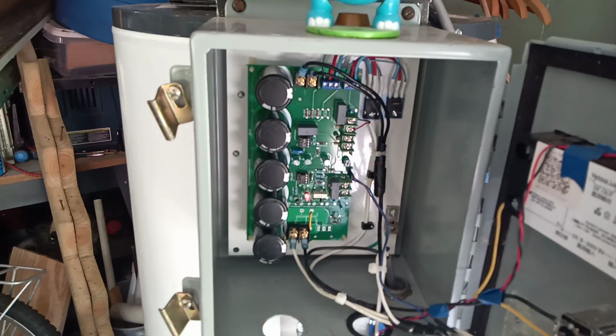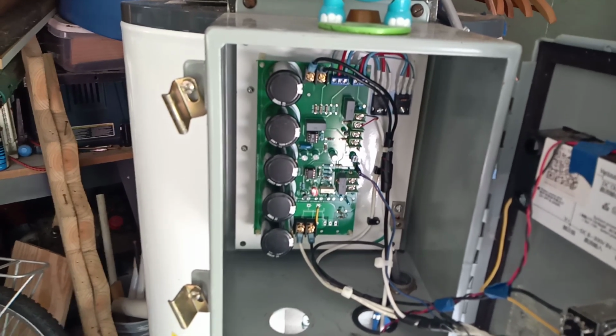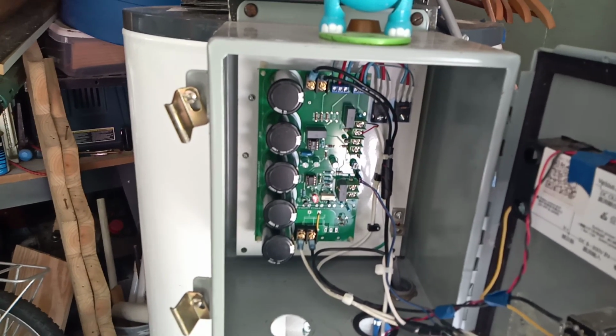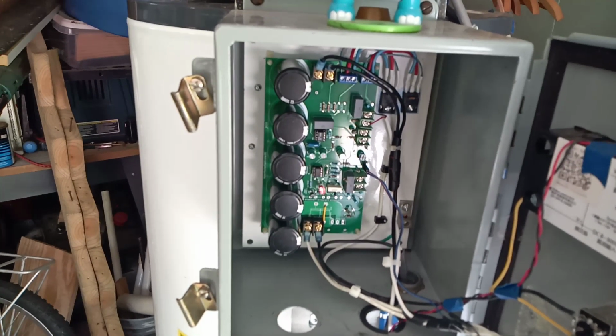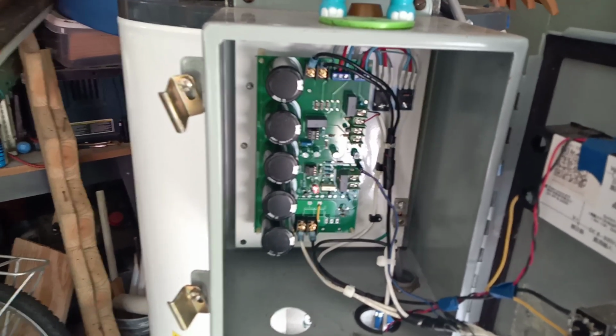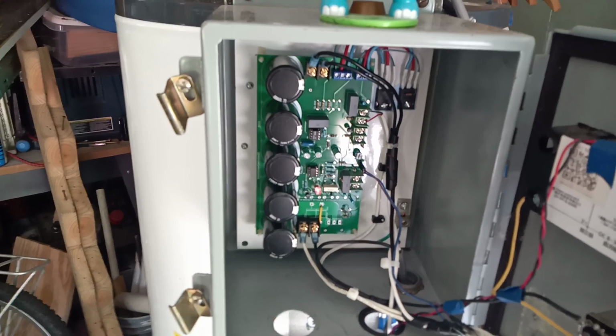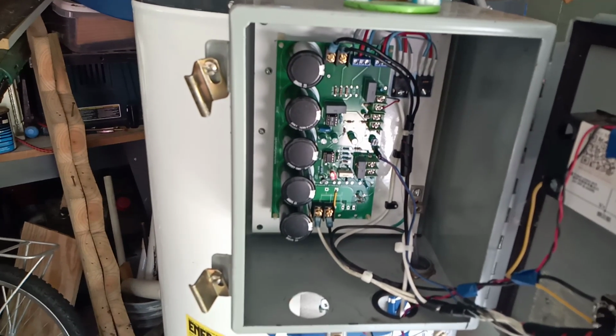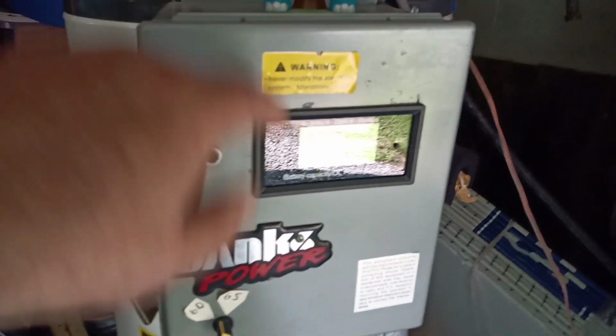When it sees the PV voltage go over what it thinks the power point voltage should be, it starts drawing just enough current to bring the power point voltage back down to what it thinks is normal. So a lot of times it's at 62.5 volts.